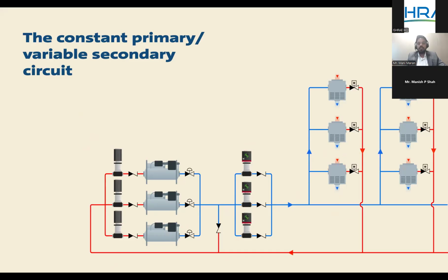Again, we have a DP sensor on the critical load or furthest index. We take that and give that as feedback to the secondary pump, and it modulates based on the change in the load. Pretty simple design, but the same challenge that we see in variable primary is still there. And on top of it, since the primary is fixed speed, the delta T is compromised most of the time, when you have a chiller running at full speed but on your secondary the load is much lower than the full speed of the chiller. So the energy is compromised again.